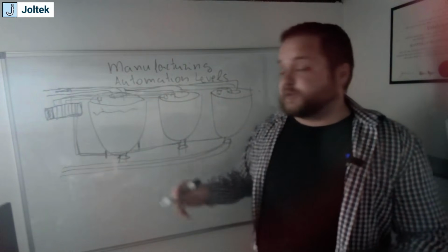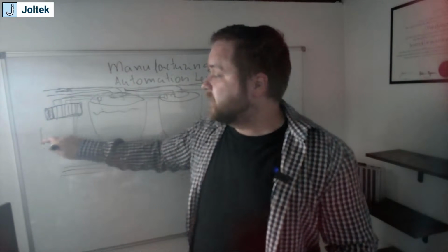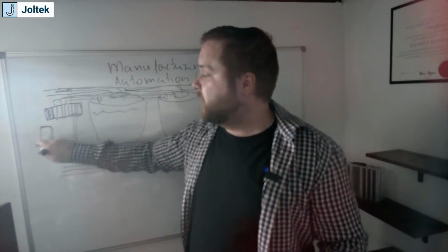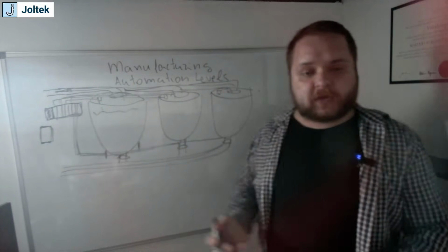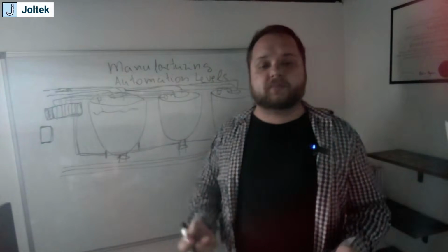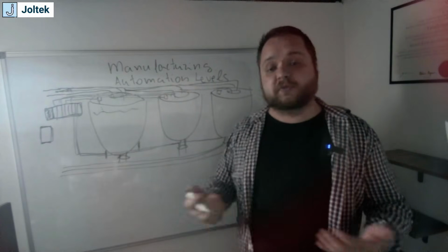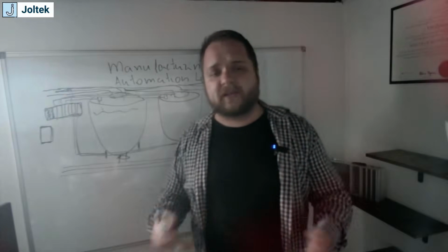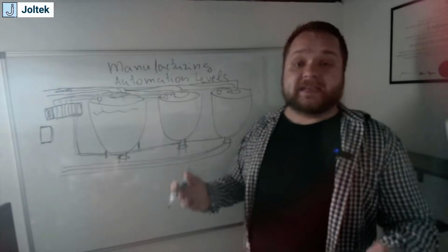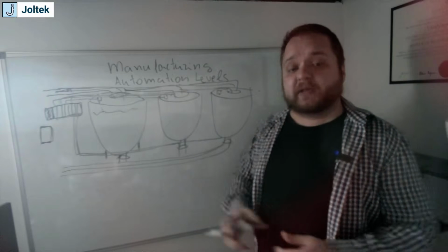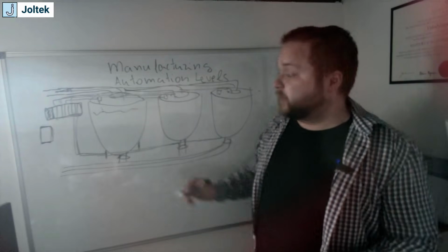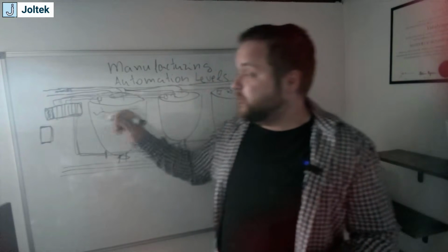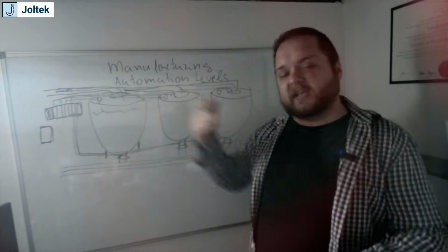And so, of course, as soon as you introduce VFDs, as I mentioned a little bit before, the easiest option, or I would say the most common option in larger facilities, is to do it over Ethernet. So if you have a drive that can talk over Ethernet/IP or Profinet or Profibus, I'm just using Ethernet in a general sense because Allen Bradley is a platform that I've been working with for a very long time. So you need a network, but ultimately, let's take again a step back.